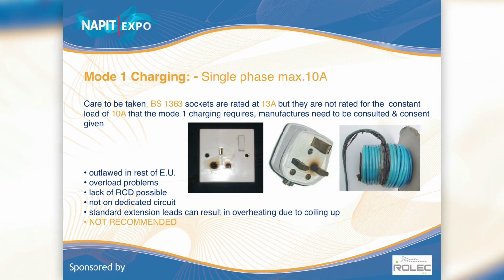In the book, it talks about different modes of charging. There are 4 modes. Mode 1 is a normal plug-in 13 amp socket. This country is the only one that has this mode, and it will one day be outlawed here very soon. The problem is BS 1363 sockets are not made to take a constant current load - they're designed for on-off use at 5 or 10-minute intervals. These charging devices require at least 10 amps, and if you're drawing 10 amps continuously, you get the results shown in the pictures.